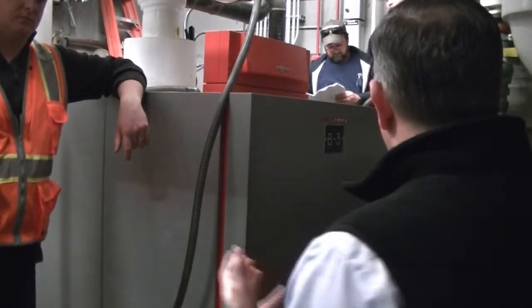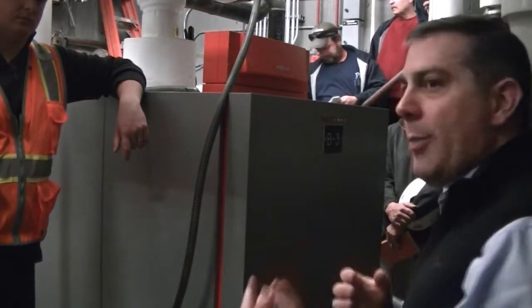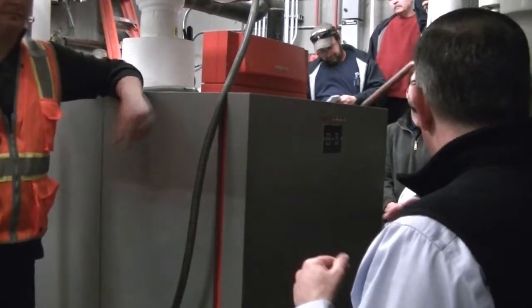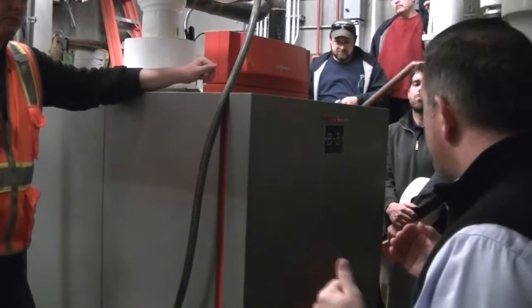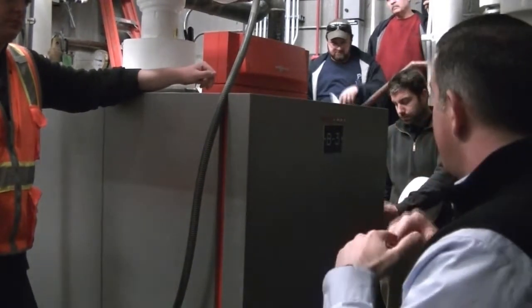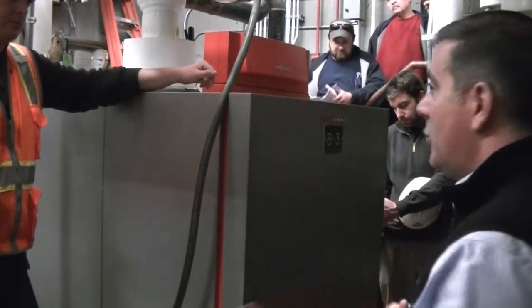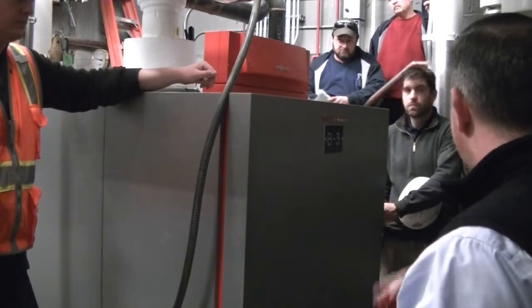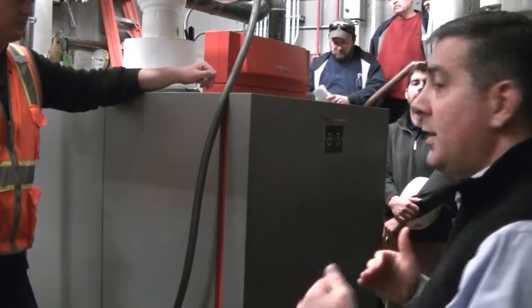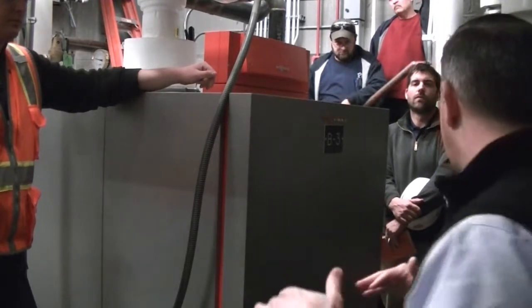So that's the one thing, if you're watching these boilers and you're thinking they're going to operate like your typical boilers, this is the one thing that's a little bit different with condensing boilers. Because it's more efficient to run condensing boilers at a lower input, you may come down here on a mild day and see 2, 3, or 4 boilers running. The difference is that they're running at low fire potentially.